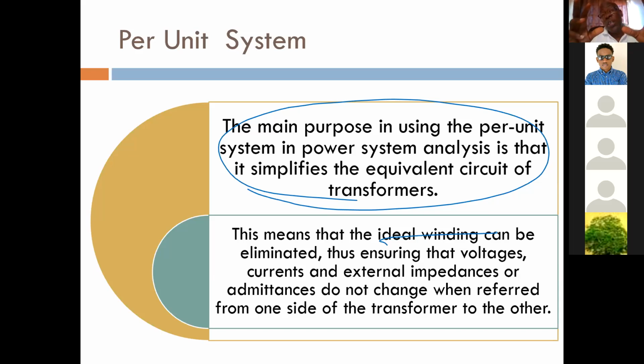So in referring an impedance, looking at an impedance across a transformer, you would square the turns ratio. But in power systems, if you were to do that, I guarantee you wouldn't complete one problem. So what we do is use the per unit representation, and the per unit impedance of your transformer will be the same whether you're looking at it from the primary or the secondary side.